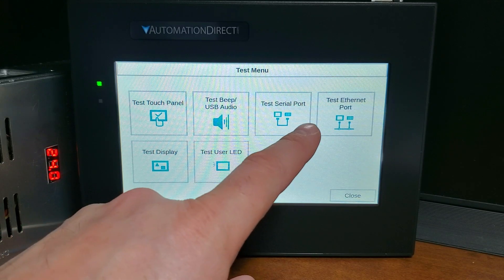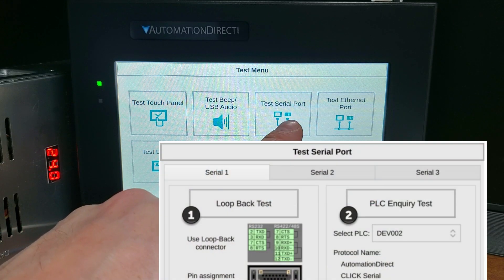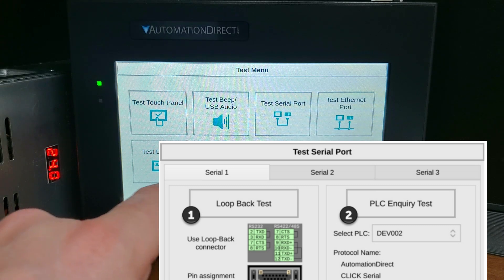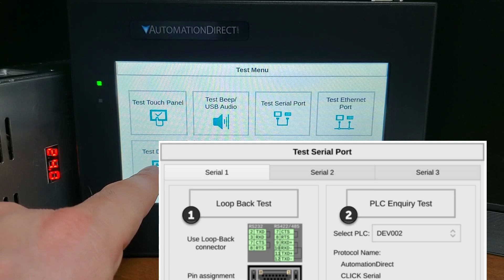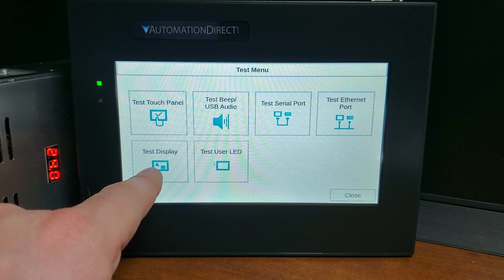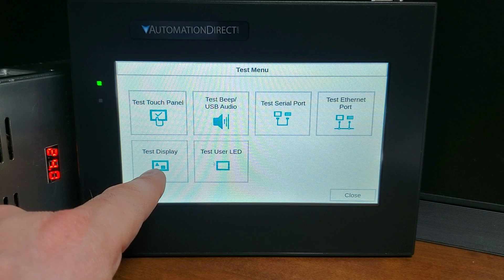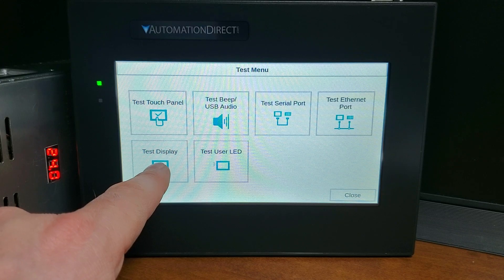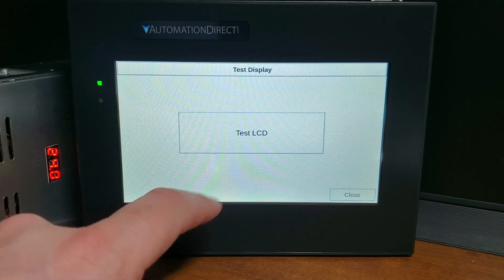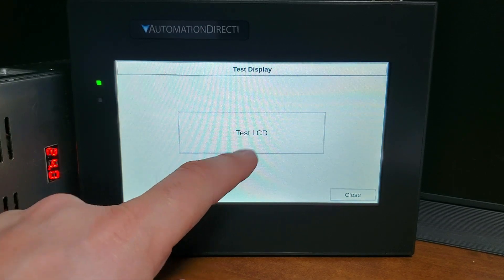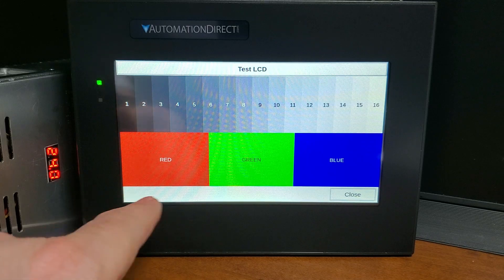Test communication port: you can test the serial and Ethernet ports for communications, though some of these options require wiring to perform the loopback tests. Test display: two different test patterns may be run on the display to allow you to check for display screen defects.